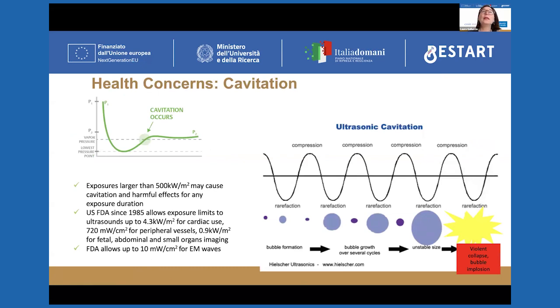Another concern that needs to be considered when using ultrasonic waves is the possibility of reducing the risk of incurring cavitation. Cavitation basically means that, due to the compression and rarefaction caused by these mechanical waves, there is the possibility of bubble formation, and these bubbles keep having unstable sizes, and thus in principle they could lead to a violent collapse. They can lead to kinetic energy effects due to bubble implosion. So in order to reduce the risk of incurring this type of issues, the exposure should be limited. And again, here I've reported some FDA recommendations in this sense.